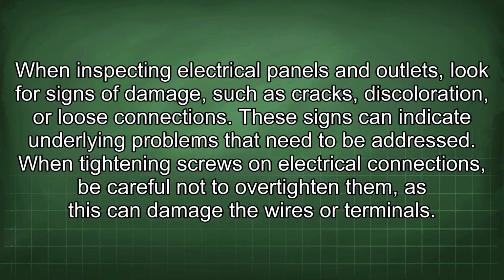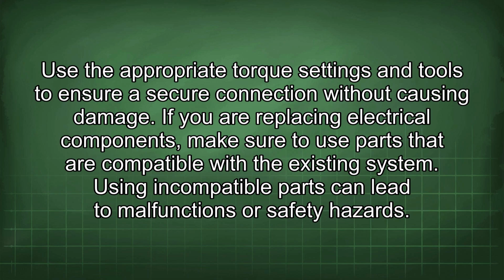When inspecting electrical panels and outlets, look for signs of damage such as cracks, discoloration, or loose connections. These signs can indicate underlying problems that need to be addressed. When tightening screws on electrical connections, be careful not to over-tighten them, as this can damage the wires or terminals. Use the appropriate torque settings and tools to ensure a secure connection without causing damage. If you are replacing electrical components, make sure to use parts that are compatible with the existing system. Using incompatible parts can lead to malfunctions or safety hazards.